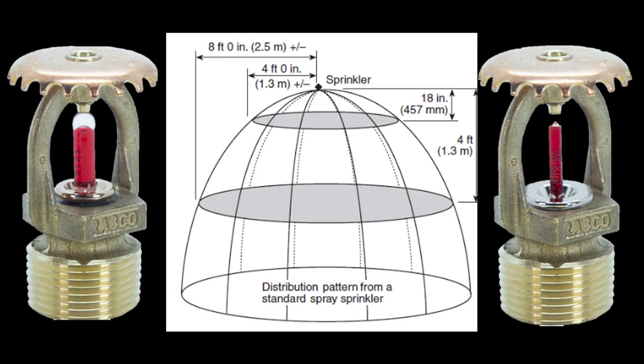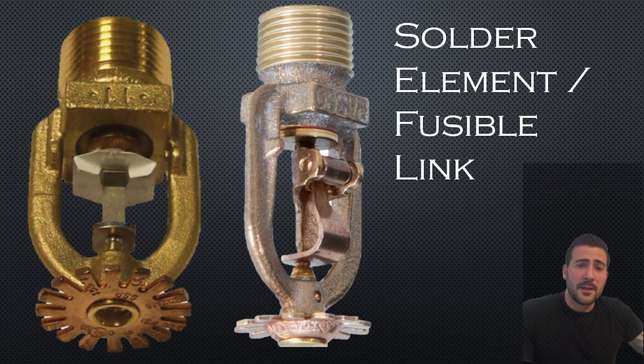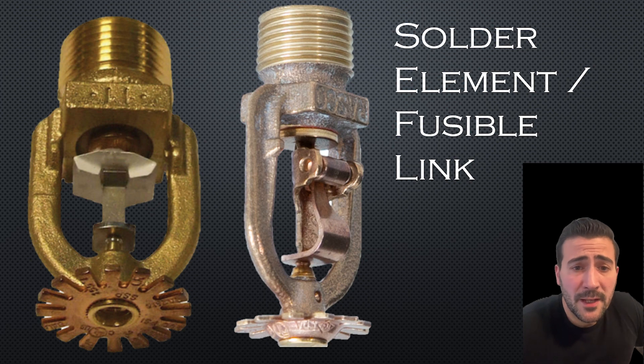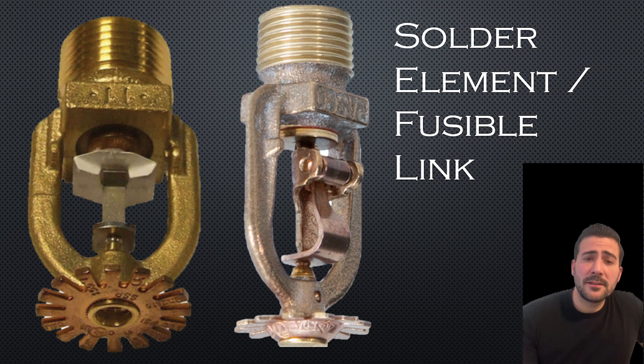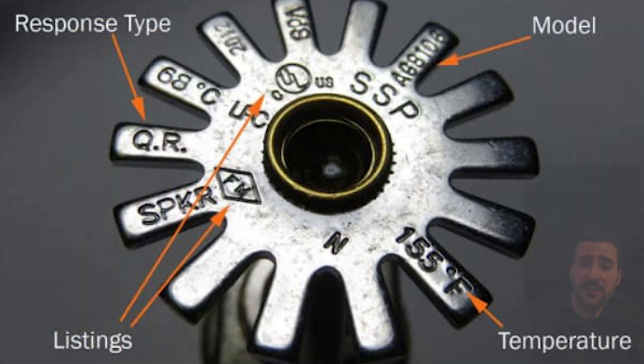The deflector and the spray pattern are exactly the same. If you have a fusible link style element, you can look at its deflector to see if it's stamped with QR for quick response or SR for standard response — and that's how you can tell the difference.